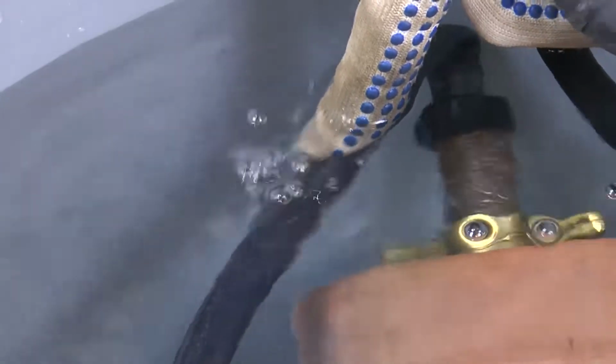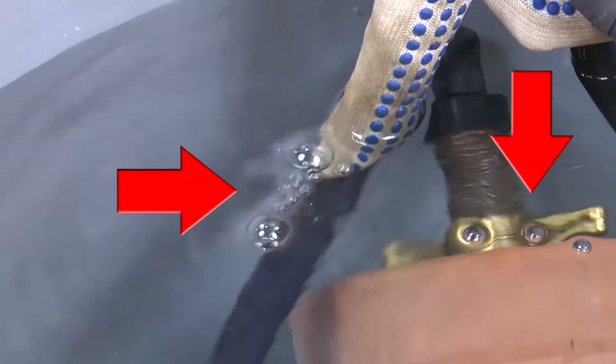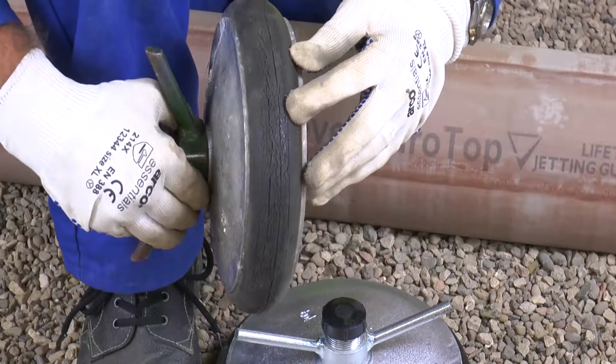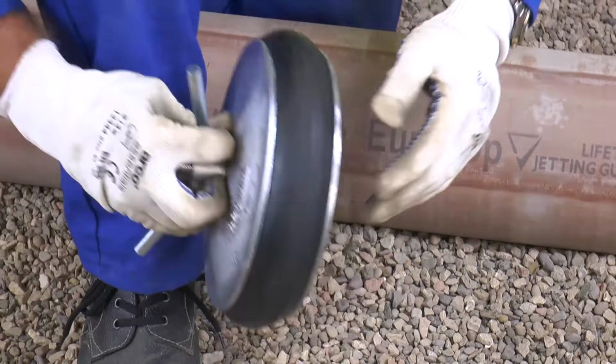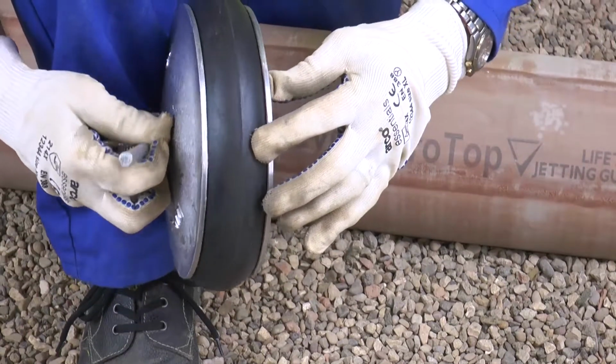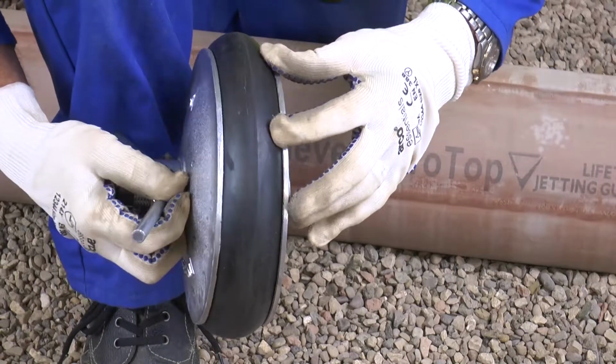This rubber tubing has a hole in it, but it could be cracked or split, and the stopper is poorly fitted. The bung may have surface cracks in the rubber, or it may not be tight enough. Some steel-plated stoppers can be deformed by over-tightening, and not compress the rubber stopper adequately to provide a seal.